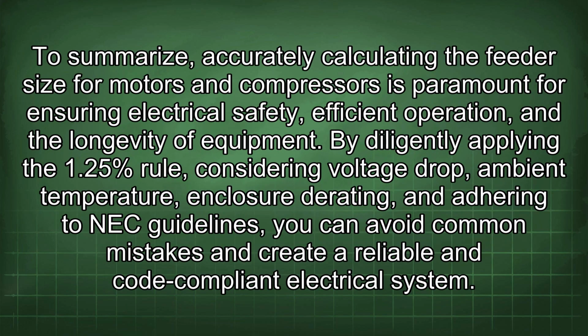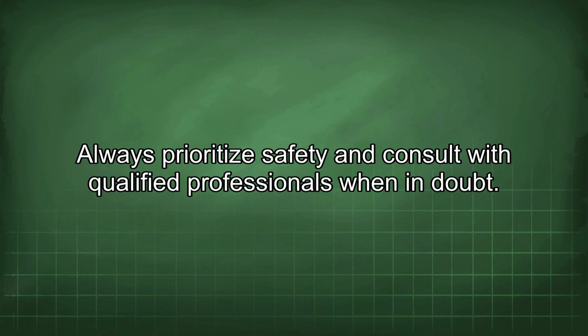To summarize, accurately calculating the feeder size for motors and compressors is paramount for ensuring electrical safety, efficient operation, and the longevity of equipment. By diligently applying the 125% rule, considering voltage drop, ambient temperature, enclosure derating, and adhering to NEC guidelines, you can avoid common mistakes and create a reliable and code-compliant electrical system. Always prioritize safety and consult with qualified professionals when in doubt.